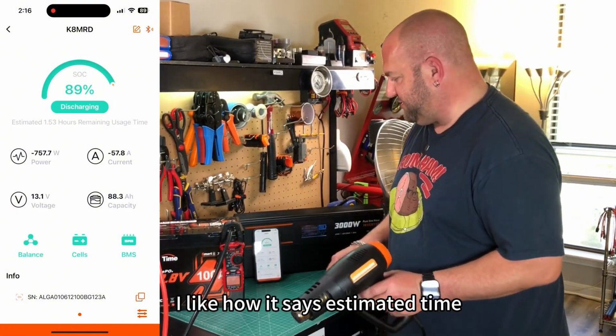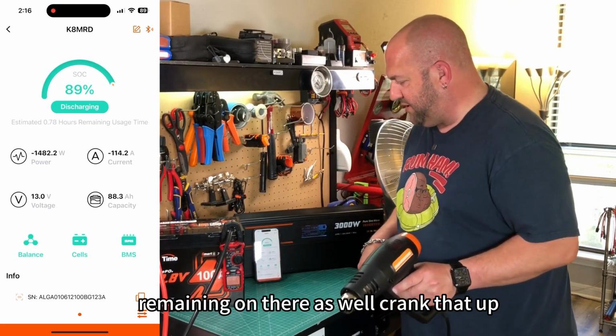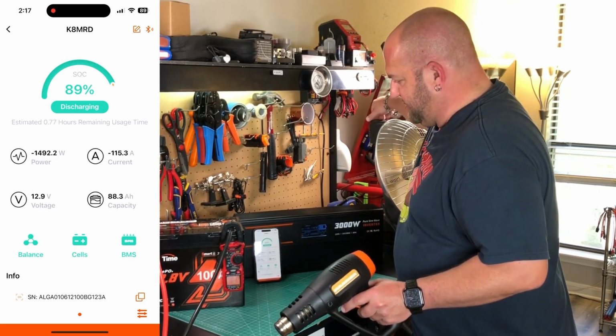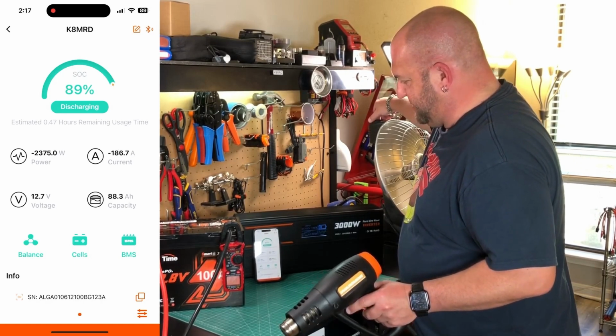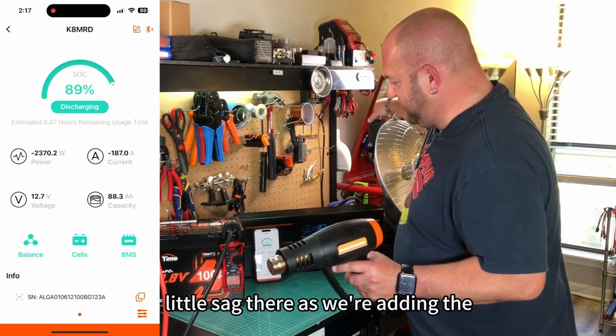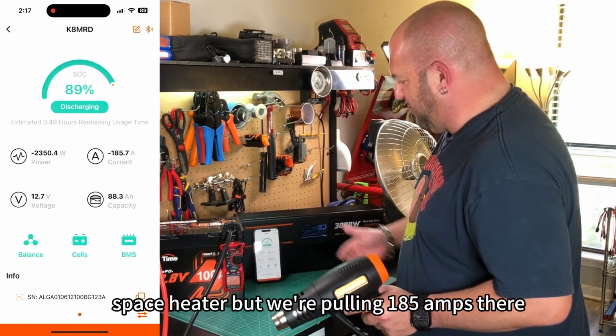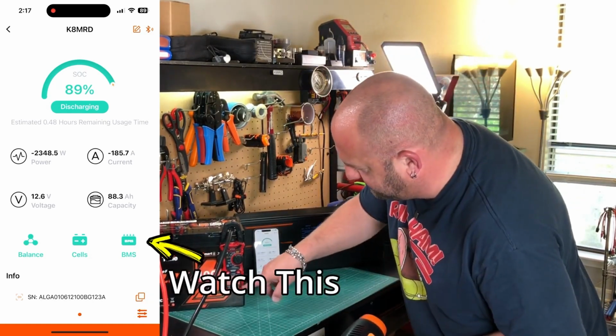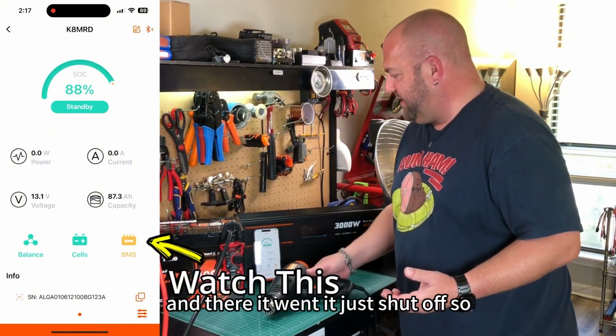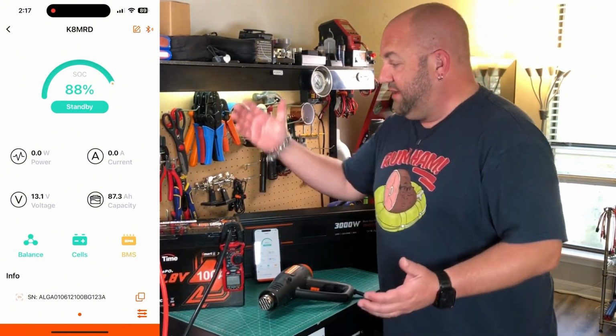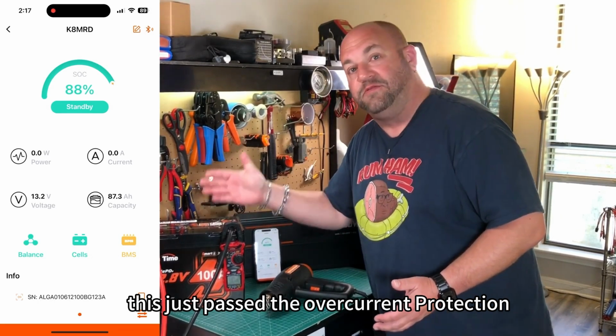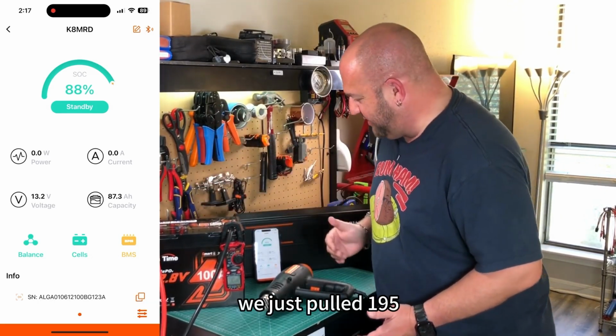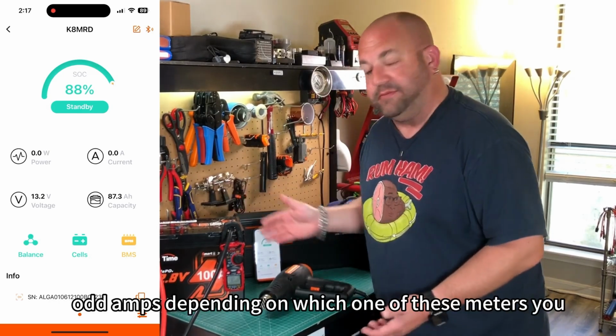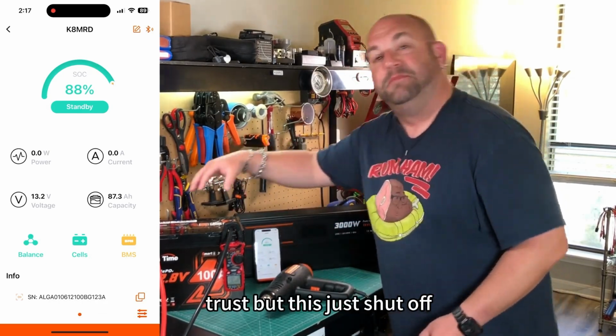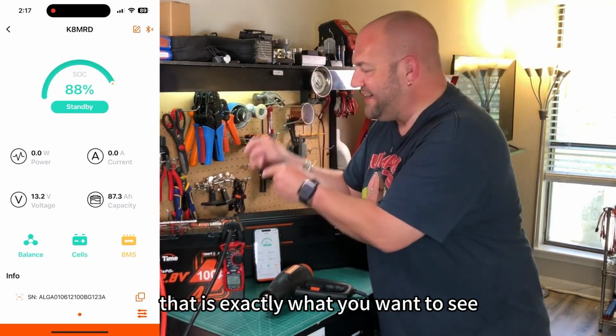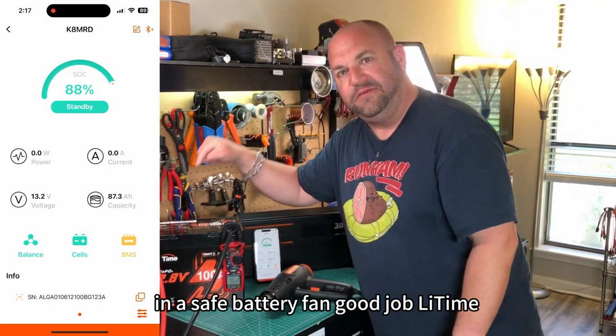I like how it shows estimated time remaining on there as well. Let's crank this guy up. There's a little sag as we're adding the space heater, but we're pulling 185 amps there. My meter says 195, and there it went, it just shut off. So this just passed the overcurrent protection. We pulled 195, or 180-some amps depending on which meter you trust, but this just shut off. That is exactly what you want to see in a safe battery.